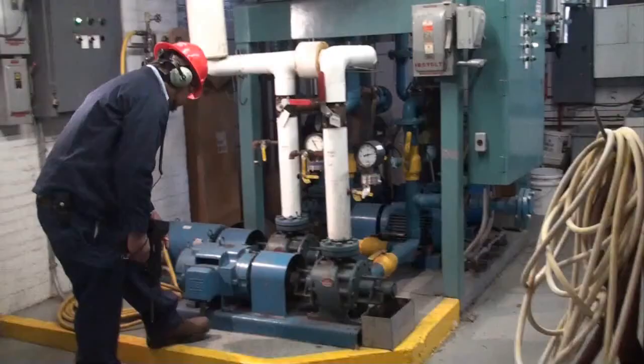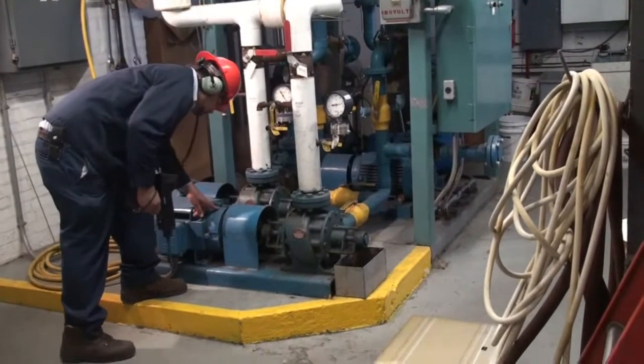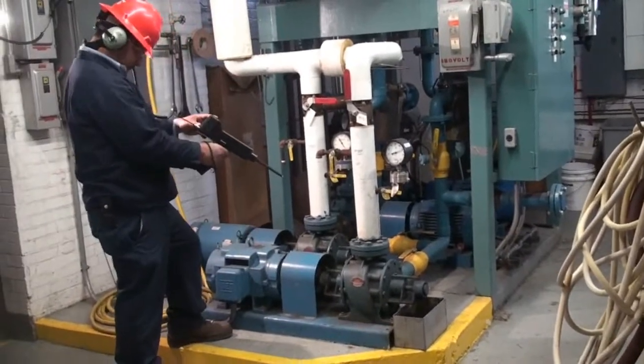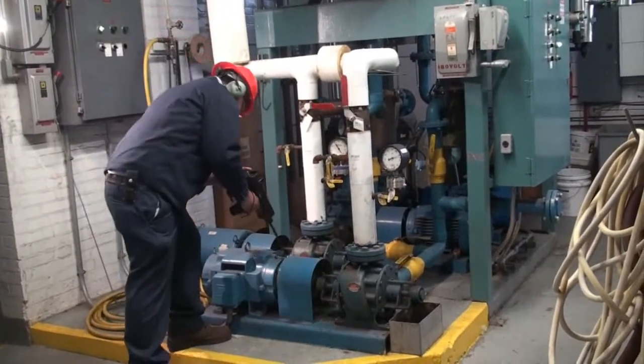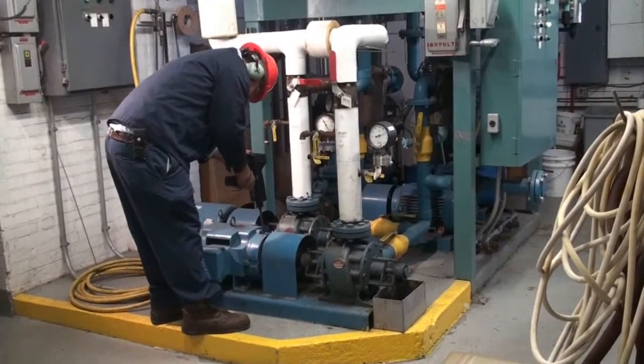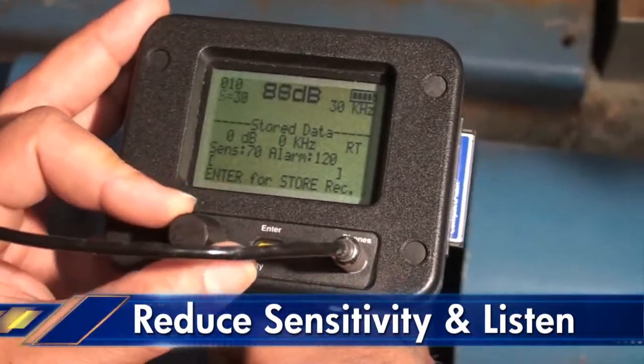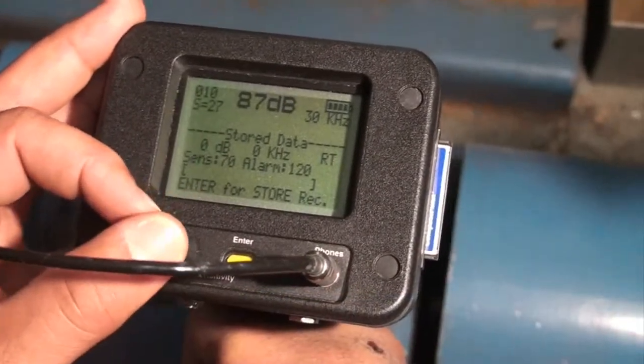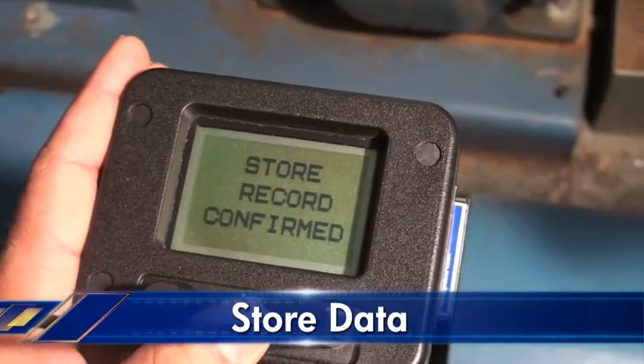Now let's go and check a bearing. First we'll check the identification tag to see if it conforms to the test number in our route. Then we'll touch the bearing and reduce the sensitivity to hear the bearing more clearly. When ready, we'll store the data, which we can then download into our software.